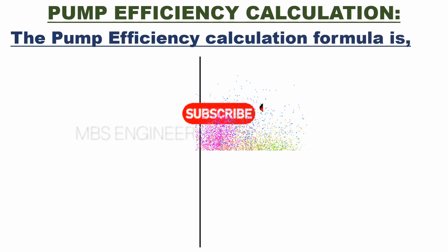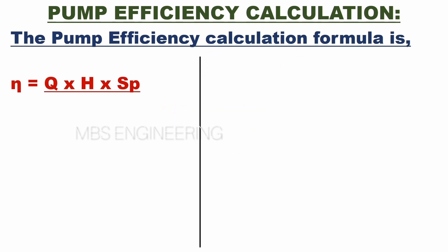We learn the formula for pump efficiency calculation for the centrifugal pump. Eta is equal to Q into H into specific gravity, and the obtained value is divided by 367 into brake kilowatt.